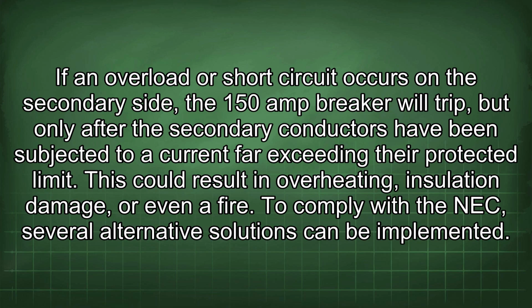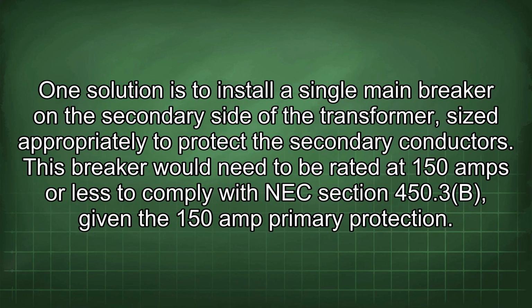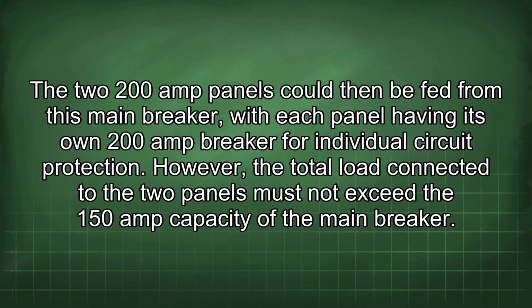To comply with the NEC, several alternative solutions can be implemented. One solution is to install a single main breaker on the secondary side of the transformer, sized appropriately to protect the secondary conductors. This breaker would need to be rated at 150 amps or less to comply with NEC Section 450.3b, given the 150 amp primary protection. The two 200-amp panels could then be fed from this main breaker, with each panel having its own 200-amp breaker for individual circuit protection.